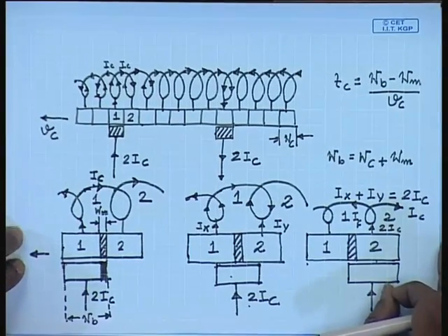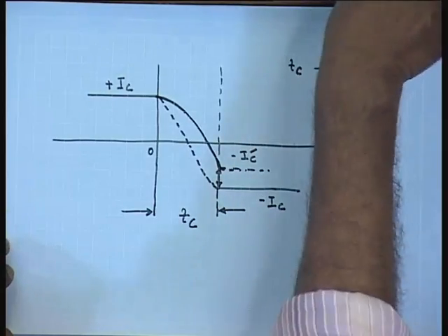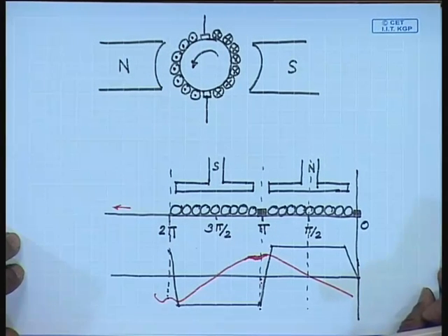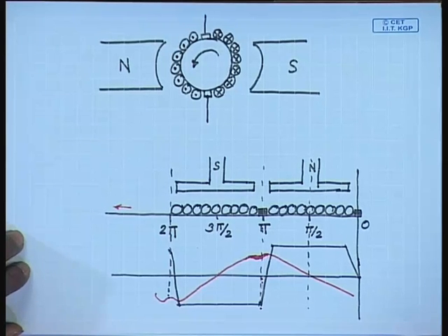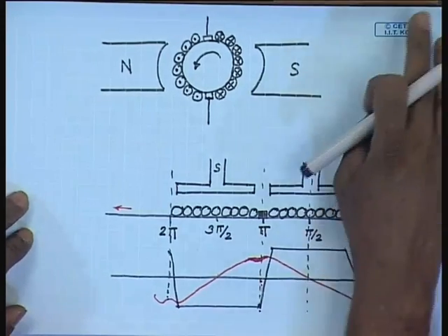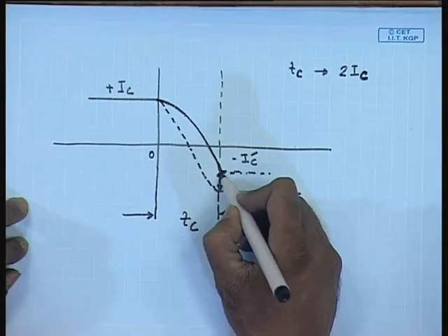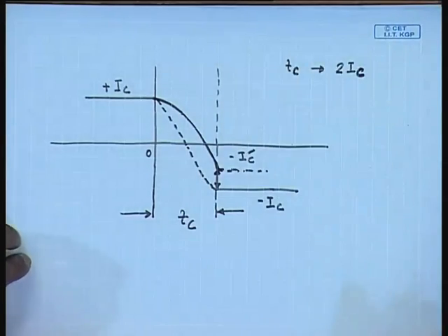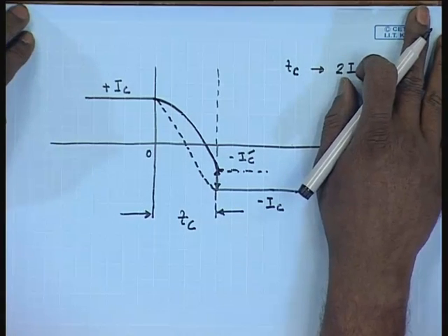Not only the leakage inductance of the coil, due to armature reaction, we have seen that the armature reaction flux leaves a residual flux at the interpolar axis, which is of the same polarity as the pole left behind in the generating mode. So, there will be a voltage induced in the coil undergoing commutation, which will prevent or delay the change in the current in the coil undergoing commutation, leading to under commutation. As we have said that the effect of undercommutation is to produce spark, this is to be avoided.